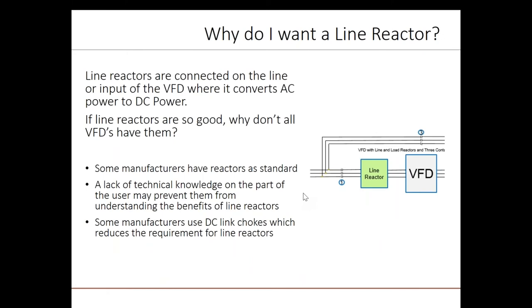Line reactors are found on the line, or input, of the VFD, where it converts AC power to DC power. A line reactor will have the effect of reducing current harmonics from the VFD flowing back toward the power system. A line reactor will also have the effect of reducing voltage transients coming from the power system that could impact operation of the VFD. If line reactors are so good, why don't all VFDs have them? Well, some VFD manufacturers do have line reactors as standard. If the user is not well-versed in the effects of poor power quality, then they may not see the benefit. If they can't see the cost-benefit justification, they will leave them out of their specification.